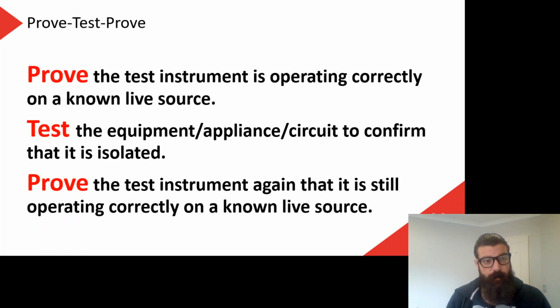I test my isolation, whatever that circuit or appliance is that I've isolated. I test there, and I'm going to test between every single terminal. So it would be phase to neutral, phase to earth, earth to neutral, to make sure there's nothing on any of those. If it's three phase, I've got to test all three phases. And again, I've discussed previously my own misadventures in failing to test every single phase and finding that one of them was switched off and two of them weren't. My bad.